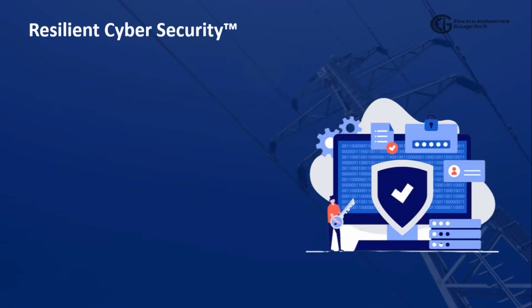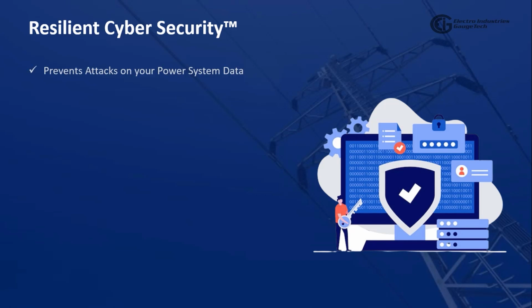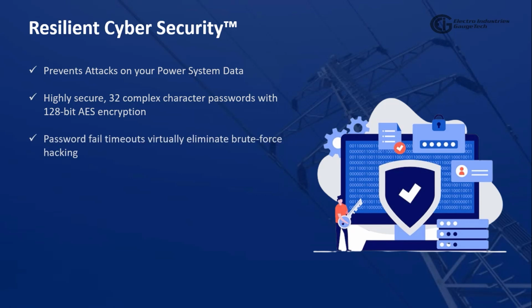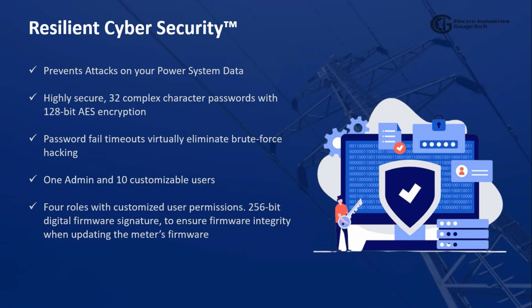The next feature is resilient cybersecurity that prevents attacks on your power system data. This is a highly secure system, with 32 complex character passwords with 128-bit AES encryption. Password fail timeouts virtually eliminate brute force hacking. An admin and 10 customizable users. 4 roles with customized user permissions. 256-bit digital firmware signature to ensure firmware integrity when updating the meter's firmware. Sealing switch and physical seals prevent remote hacking or tampering.